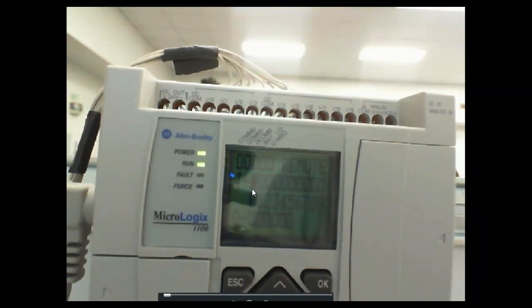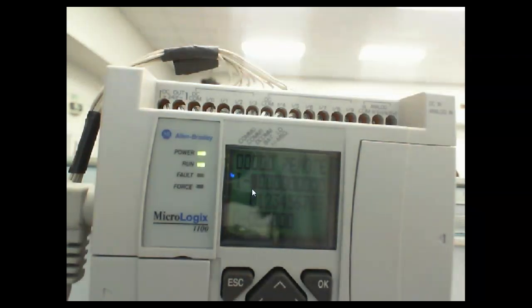So what I've got is I'm going to come up here on this PLC. By default, it comes up to this. But I'm going to select I/O status. And this right here shows me my input. So when I come over and flip that switch, you can see this turns on. So what I've done, I've just checked out without even putting out a meter, I've just checked out my sensor is okay. So I trip a sensor, and I'm seeing that it's made it to the PLC.